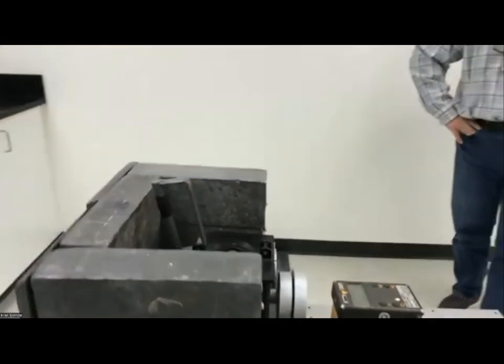That's it, yeah. So, I mean, the source itself is rated to be plus or minus 5% in terms of its delivered dose rate. And then the distance has to be within plus or minus 2%. So we're quite particular about how we position it. And if it looks like it's off, one of the first things we check is whether it's in the right position in terms of being aligned with the beam and its distance from the source. So we'll recheck those if we seem to see a potential issue.